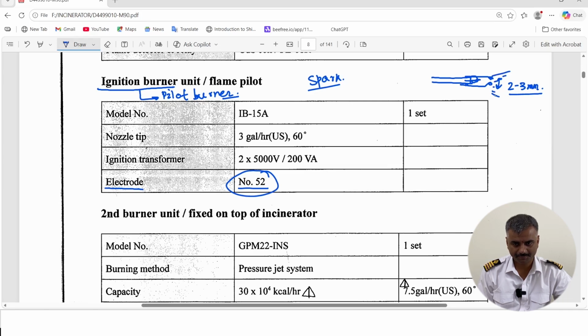The flame sensor will raise the misfire alarm, because after the spark there has to be atomization here, so that this spark can catch fire in this atomized fuel, right? So this gap has to be 2 to 3 mm. And what is the logic behind this 2 to 3 mm? Let us understand today. Air is an insulating material. But any insulating material has a breakdown potential where it will allow the voltage to pass, or it will be ionized. In case of air, it is around 3 kilovolt. So if you supply a voltage of 3000 volt across two terminals of the air, it will get ionized. Spark will be produced.